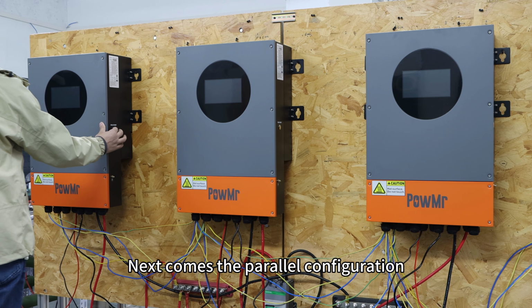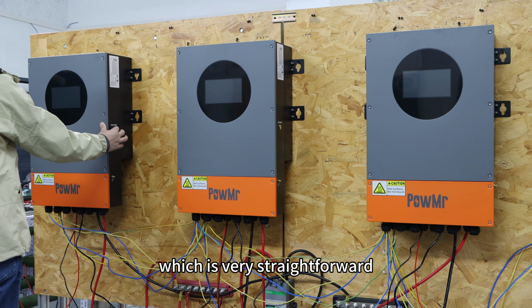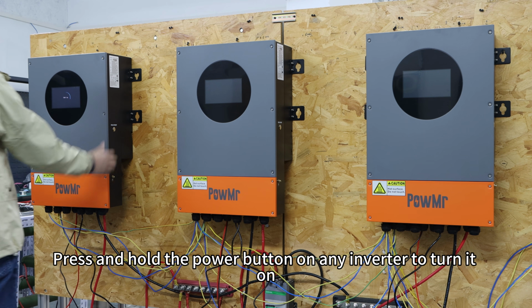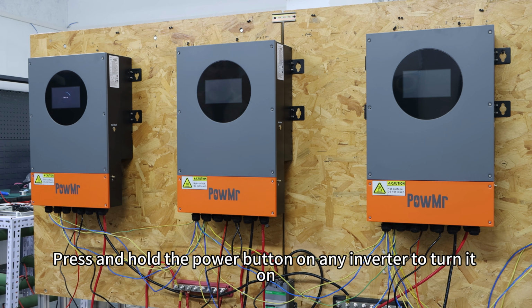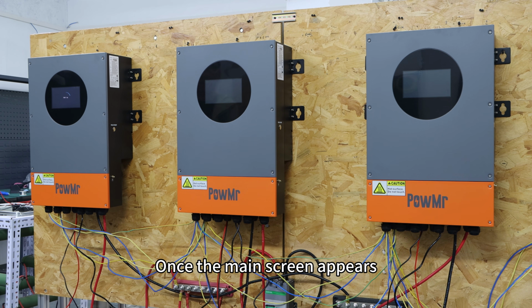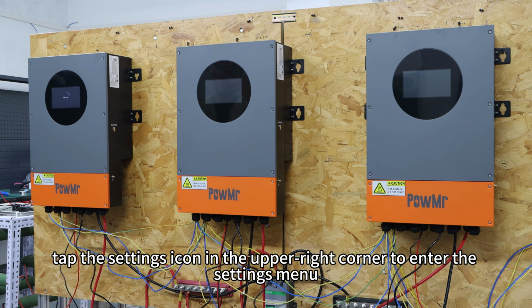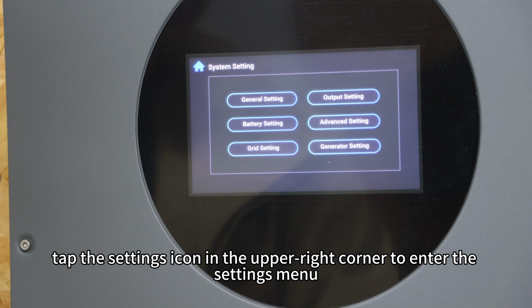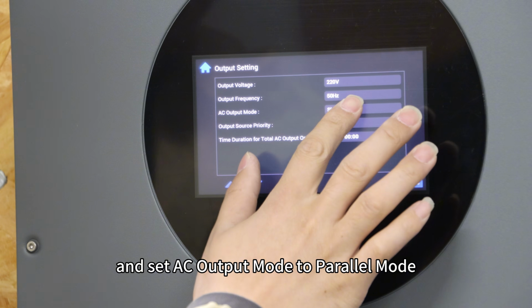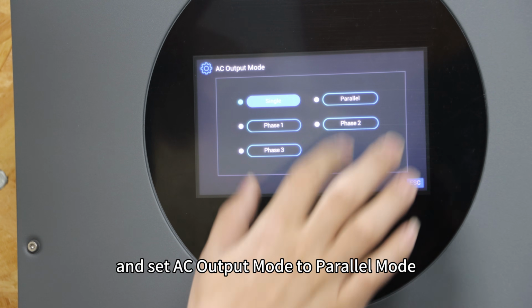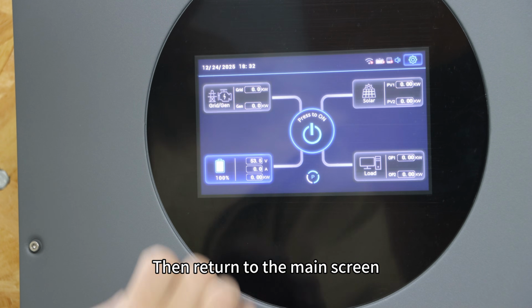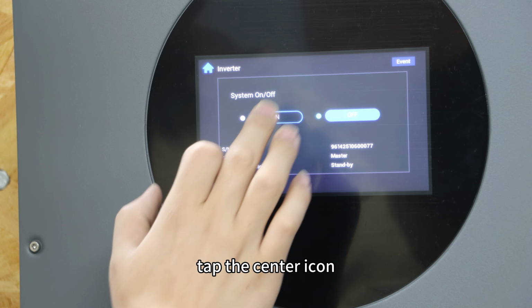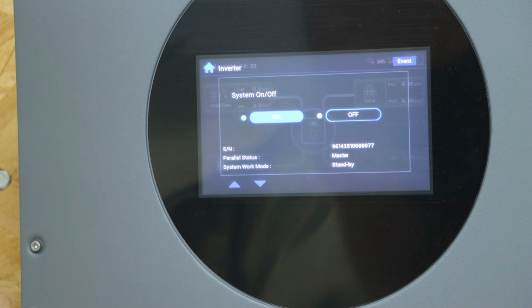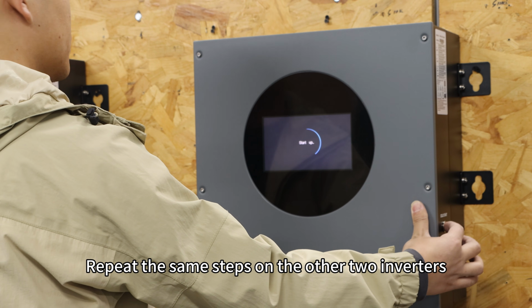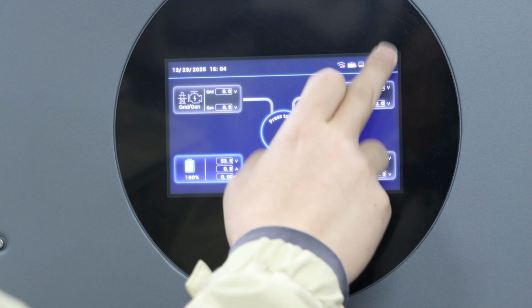Next comes the parallel configuration, which is very straightforward. Press and hold the power button on any inverter to turn it on. Once the main screen appears, tap the settings icon in the upper right corner to enter the settings menu. Go to Output Setting and set AC output mode to Parallel Mode. Then return to the main screen, tap the center icon and start parallel operation. Repeat the same steps on the other two inverters.